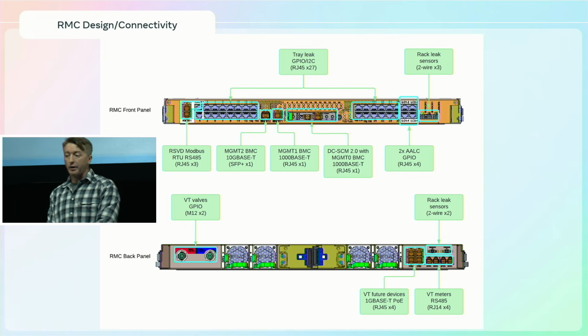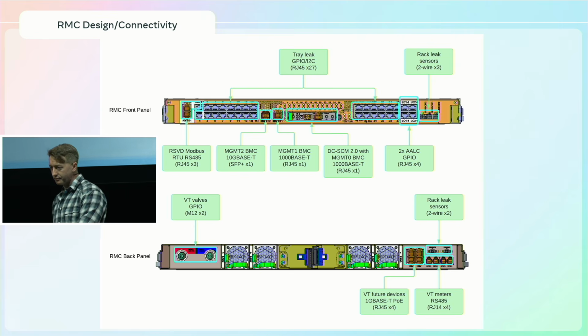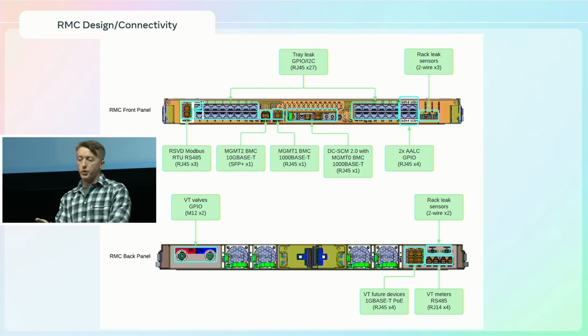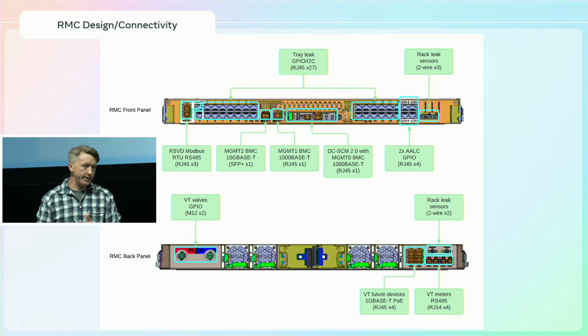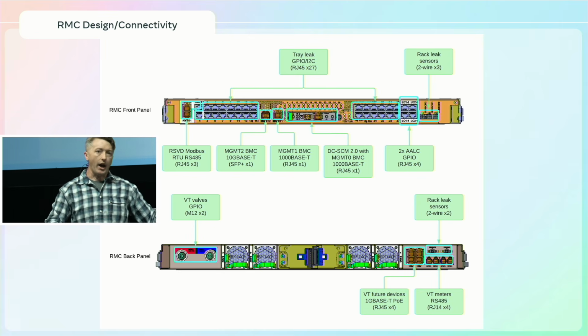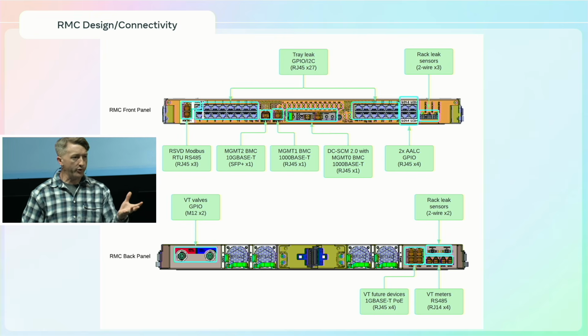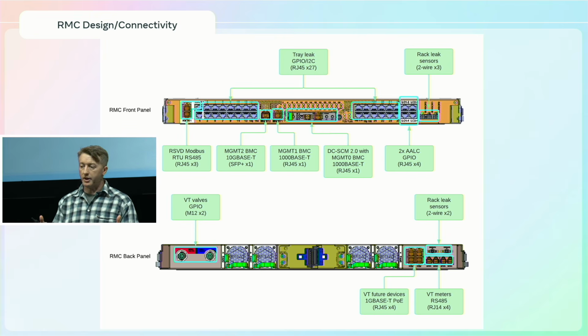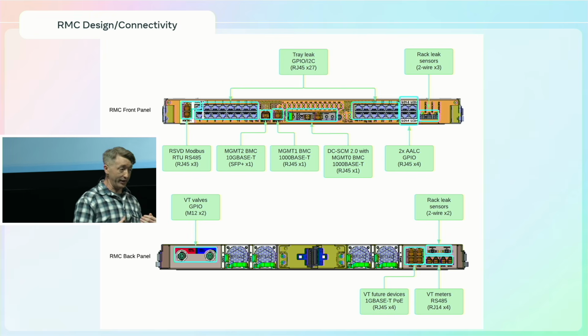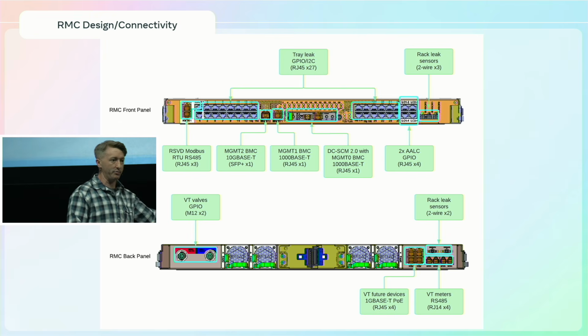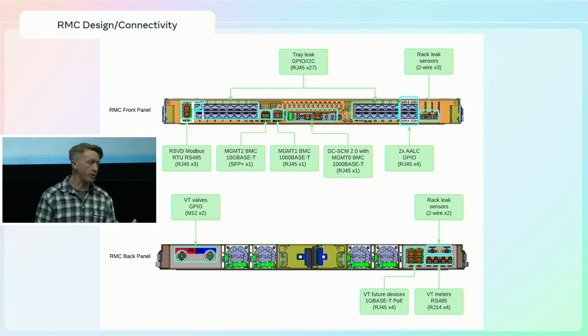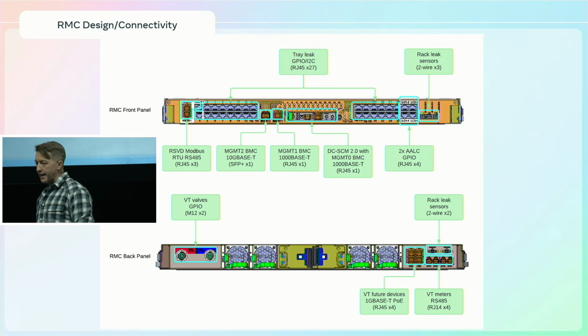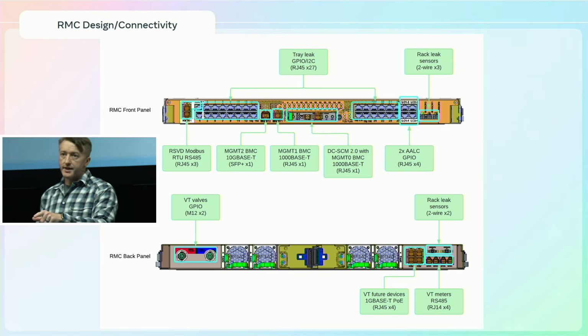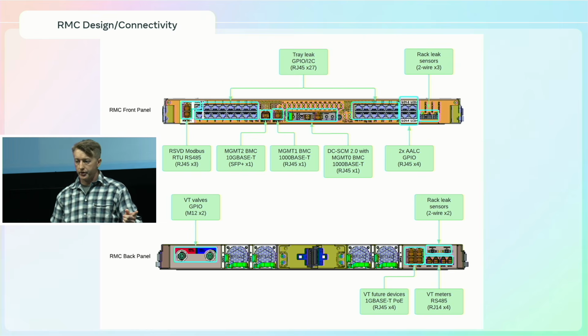This orchestrates, and it can basically command something in the rack to turn off if it sees something bad going on. This also connects to what is supplying the liquid cooling. We support both AALCs for some of our data centers. Other data centers, we have facility water that use valve trains. This has connectivity to both of those, for very similar reasons: if there's a leak, you need to stop the pumps, you want to stop the leak from occurring and making it worse. So we have both. And then the RMC itself is connected to rack-level leak sensors.